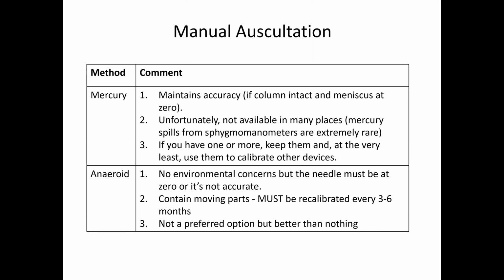Much better than nothing, but if you are using aneroid and you've never calibrated them, which happens a lot, in my clinic in Canada here, I don't think the aneroids have ever been calibrated since the building was built. And so I don't use them. I don't think anybody uses them. We use automated devices, or we have other means like a green light, and we have mercuries as well. So I think overall, if you have to use aneroid, that's fine. Just make sure it's calibrated if you at all possibly can do that. And next slide, please.